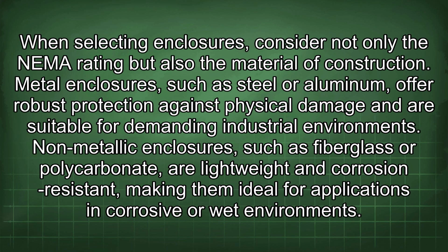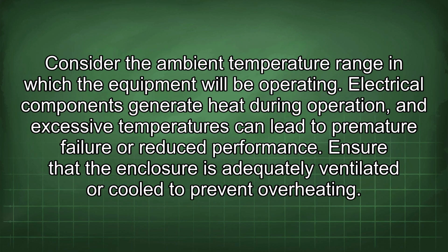When selecting enclosures, consider not only the NEMA rating but also the material of construction. Metal enclosures, such as steel or aluminum, offer robust protection against physical damage and are suitable for demanding industrial environments. Non-metallic enclosures, such as fiberglass or polycarbonate, are lightweight and corrosion-resistant, making them ideal for applications in corrosive or wet environments. Consider the ambient temperature range in which the equipment will be operating. Electrical components generate heat during operation, and excessive temperatures can lead to premature failure or reduced performance. Ensure that the enclosure is adequately ventilated or cooled to prevent overheating.